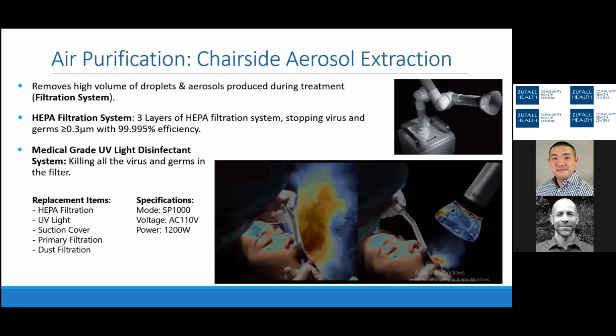So looking at the images here, I've adjusted the color a little bit, which reflects the concentration and mass of aerosols being produced. And this image here on the left shows a very large cloud or mass of aerosols. The image on the right shows a much lesser concentration. So if indeed the extraction device was pulling the same mass of aerosols through the inlet here, we would expect to see some darker brownish, yellowish colors actually being taken into the extraction inlet.